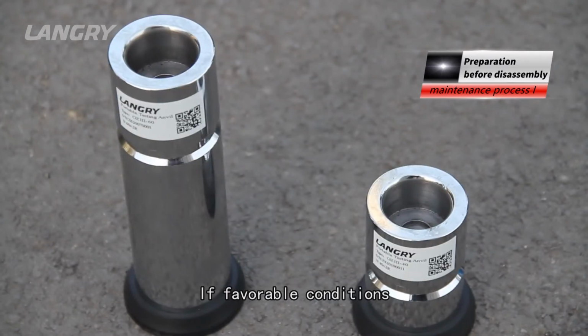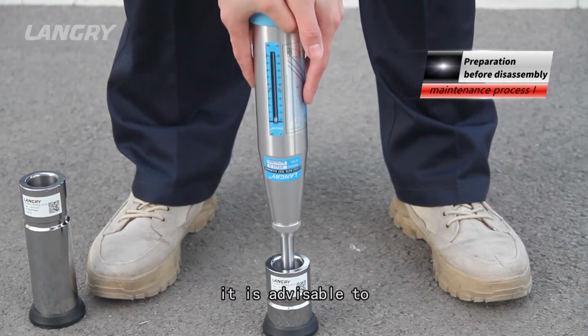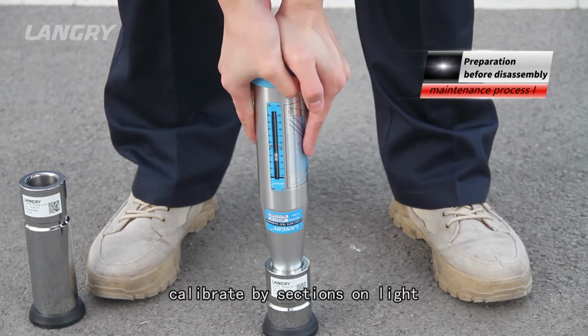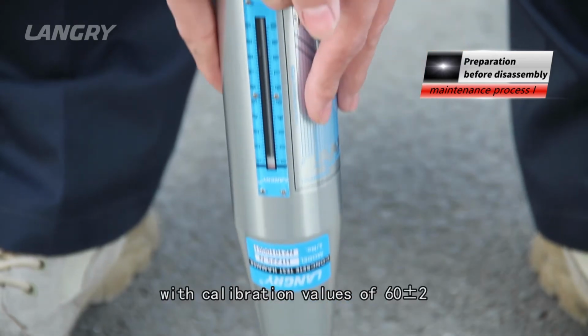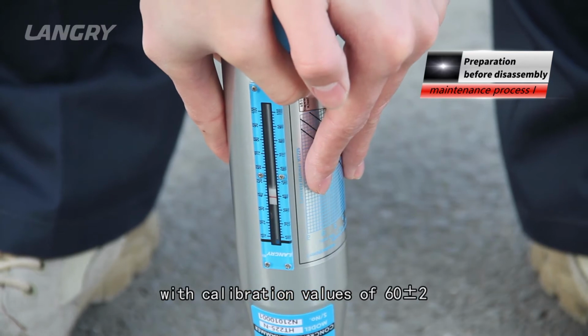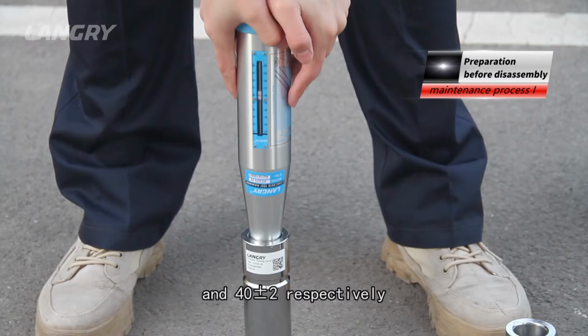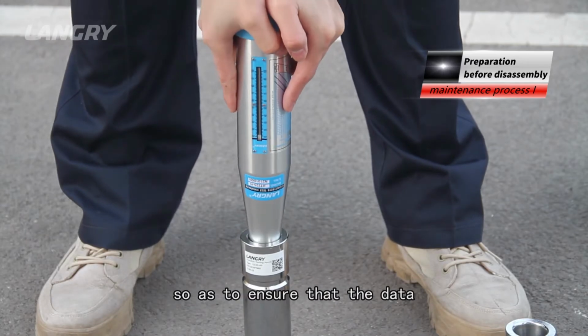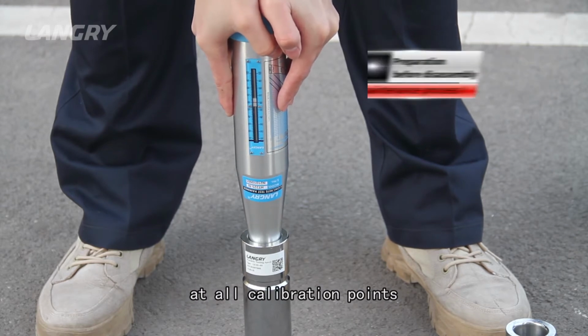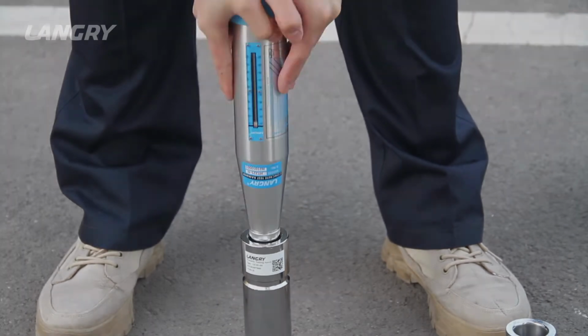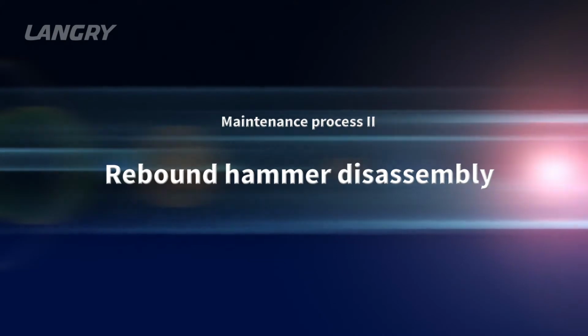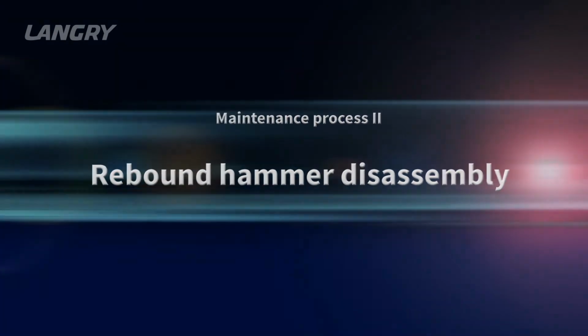If conditions are favorable, it is advisable to calibrate by sections on light and miniature testing anvils with calibration values of 60 ± 2 and 40 ± 2 respectively, so as to ensure that the data at all calibration points are accurate. Maintenance process 2. Rebound hammer disassembly.